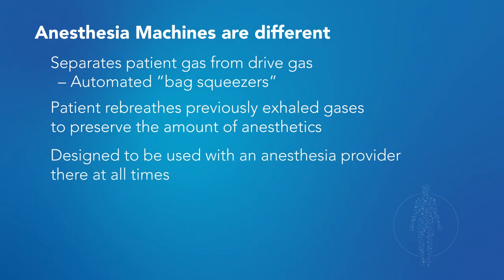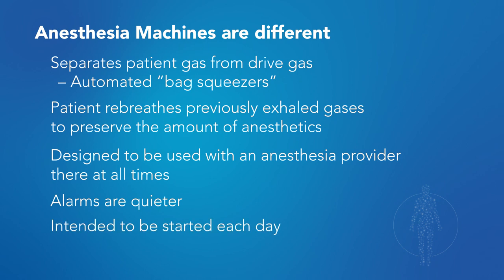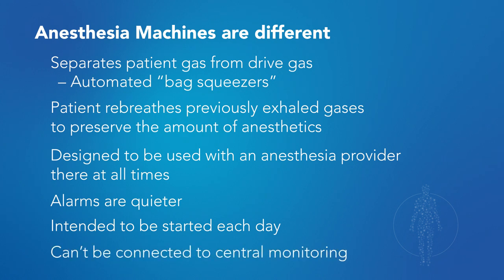Another very important difference is that anesthesia machines were designed to be used with an anesthesiologist or anesthesia provider right by the machine at all times. The alarms are set up for that, and the machine is meant to be restarted every day for use on that day's patients. It can't be connected to a central monitoring station—so the whole user interface isn't designed for unattended use the way an ICU ventilator is. Those are the two major things.